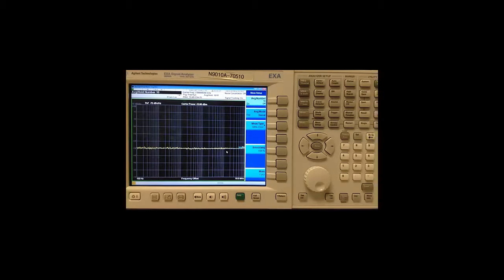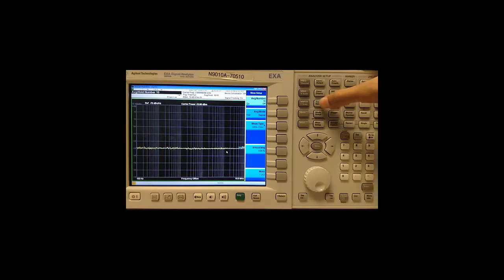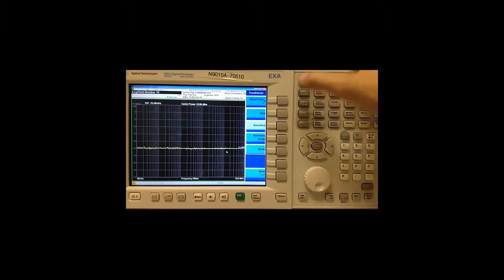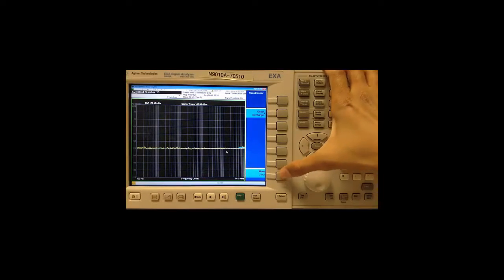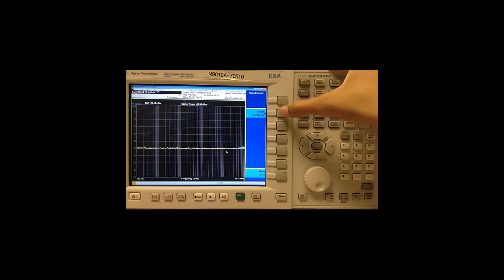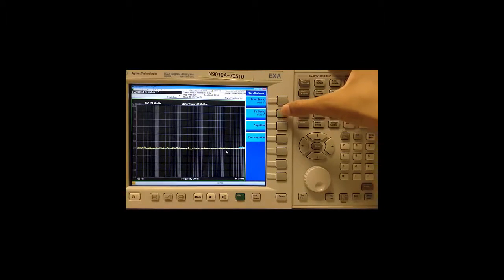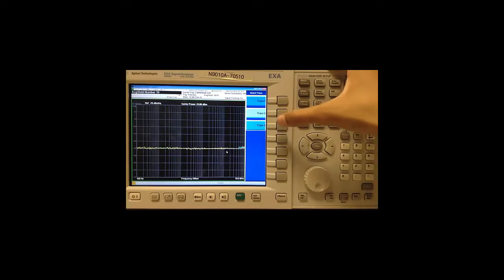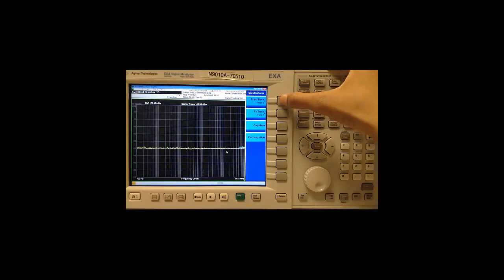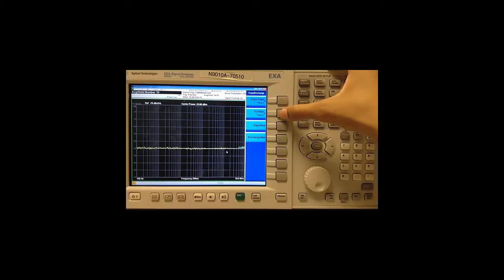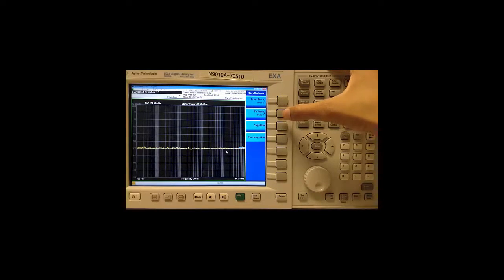Now that our average has completed, let's go to trace detector, more, copy exchange, choose trace 2 which is our smooth trace. Trace 3 is our reference trace. We copy from trace 2 to trace 3. Say copy now.